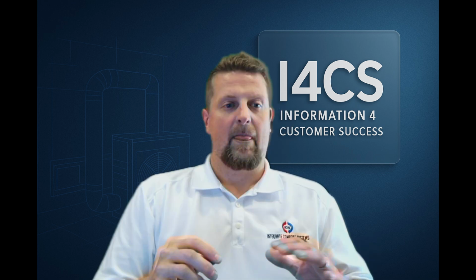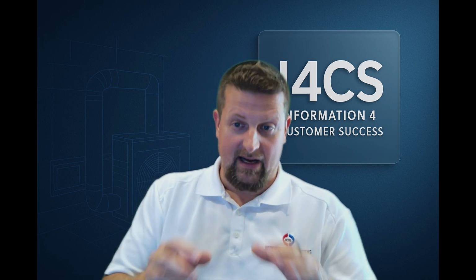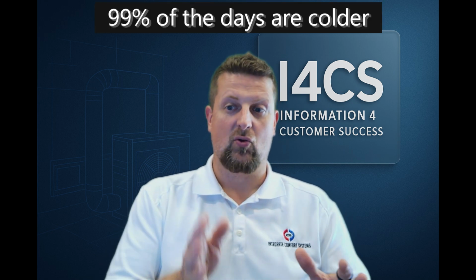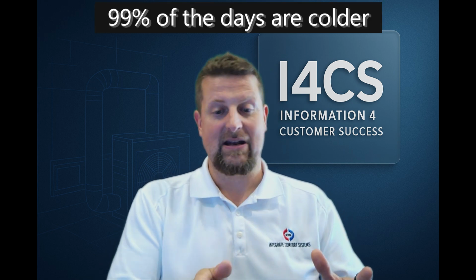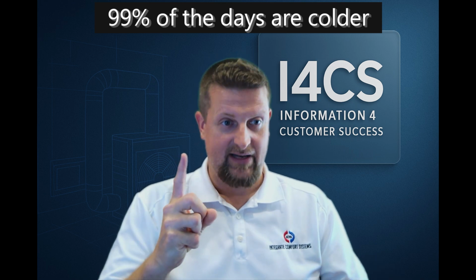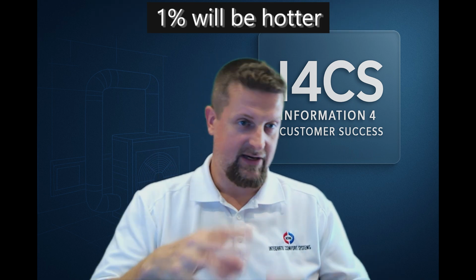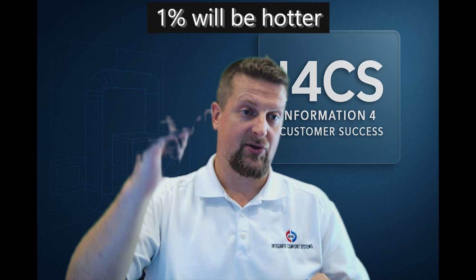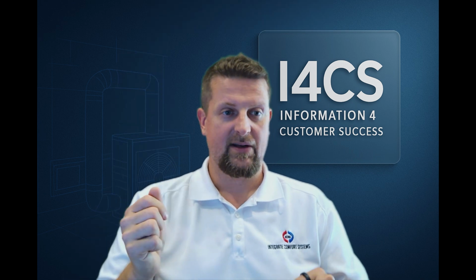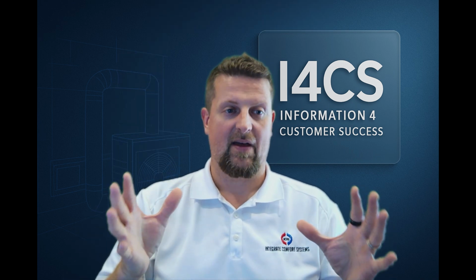Now, what does that mean? Well, this basically means that 99% of the time, the outdoor temperature is cooler than that number. It's either that number or cooler. Only 1% of the year, on the average, is going to be that temperature or warmer. So we are designing for 99% of the scenarios.